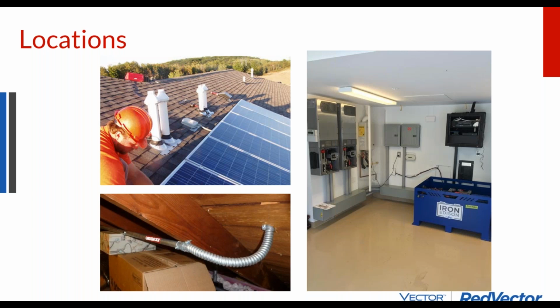Once you get inside the attic, you're now in a wet and dry environment. If you're in AC wiring, you don't even need metal protection. You can just be in Romex. DC requires metal protection. A basement is considered a damp location, and the concrete slab on the bottom can be considered a wet location due to the conductive nature of concrete. So we'll get into that.